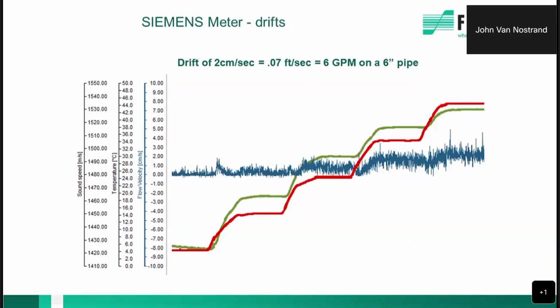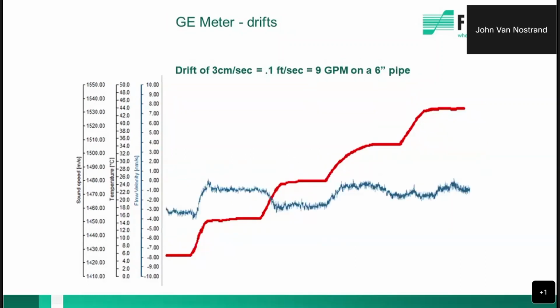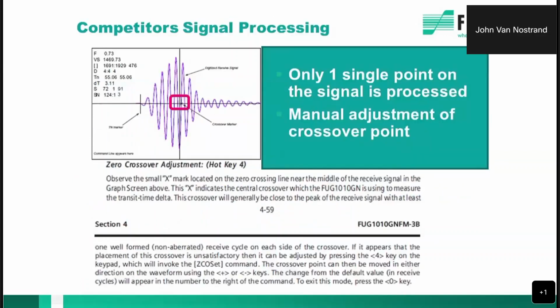A major competitor here, what we're seeing is drift over that same test, and that is 0.07 feet per second. And let's just say on a 6-inch pipe, what does that equate to? It's about 6 gallons a minute. So there's 6 gallons a minute drift built into that meter at zero when you're just sitting on the pipe. And taking a look at another manufacturer, we see a very similar result. That's 0.1 foot per second drift. That's 9 gallons a minute on a 6-inch pipe. Now imagine that on a 60-inch pipe, and you're trying to track leaks in the water system. You're basically inducing error. With the FLEXIM meter, you don't.